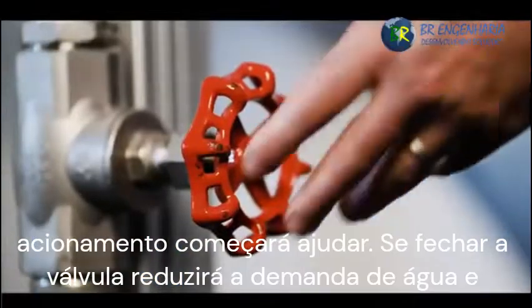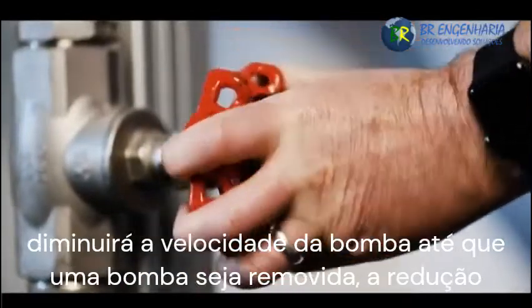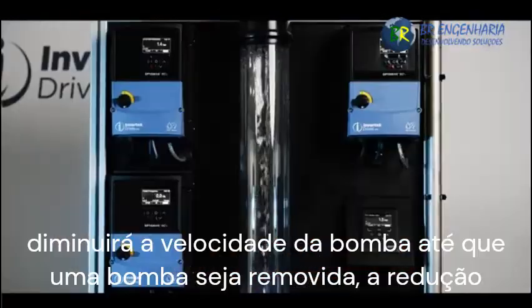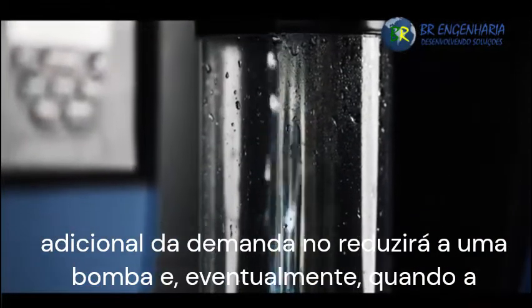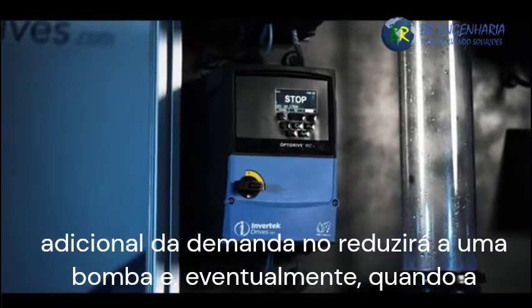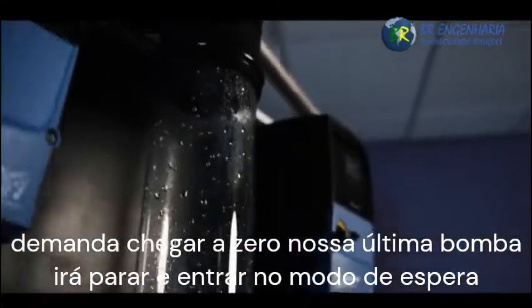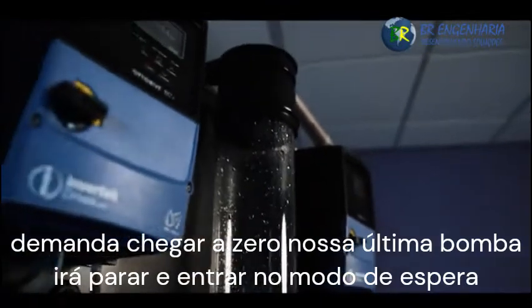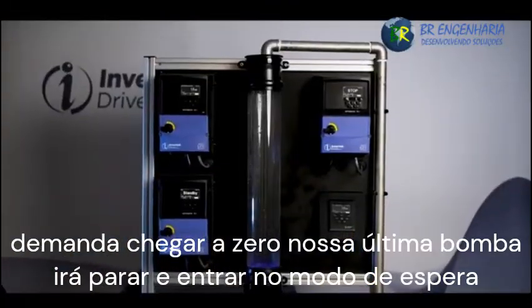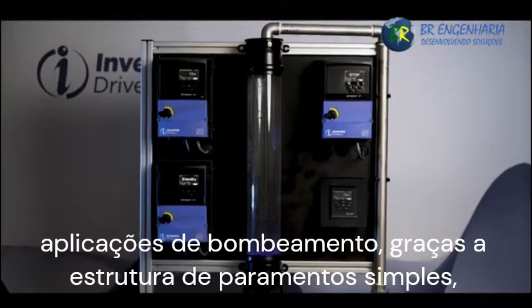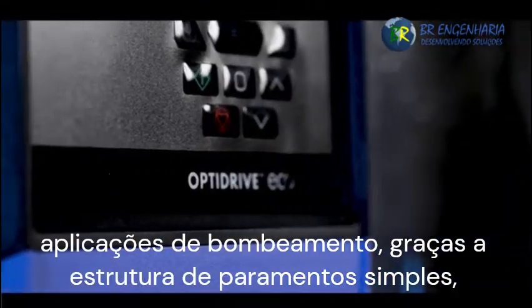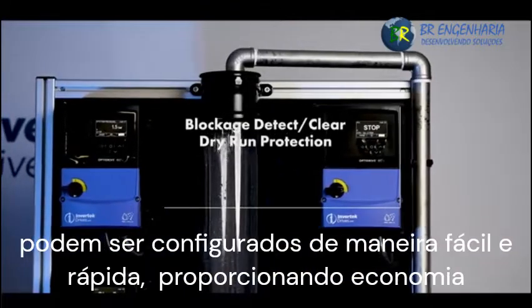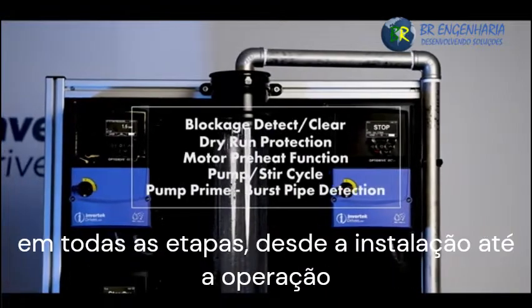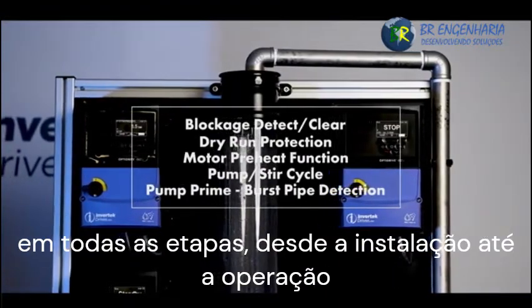Closing the valve will reduce the water demand and slow down the speed of the pump until one pump is removed. Further reduction in the demand will drop us down to 1 pump, and eventually, when the demand goes to 0, our last pump will stop and go into standby mode. The Optidrive Eco also contains many additional features designed for pumping applications. Thanks to the simple parameter structure, these can be easily and quickly set up, providing savings at every stage from installation through to final operation.